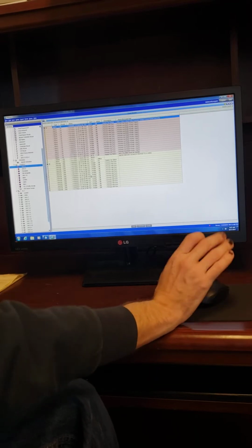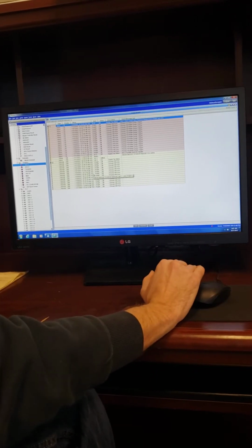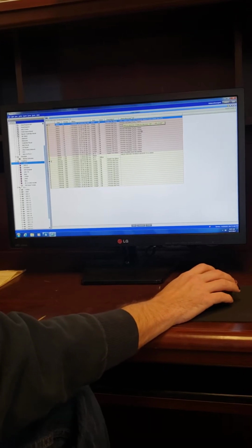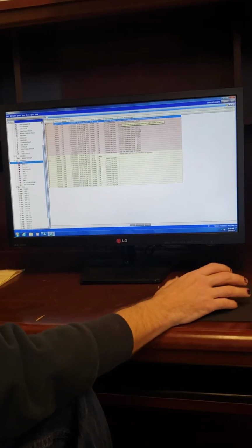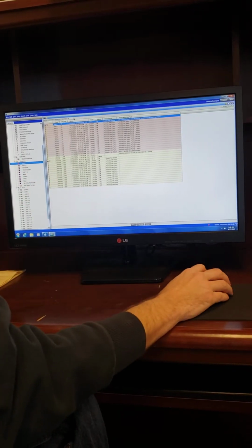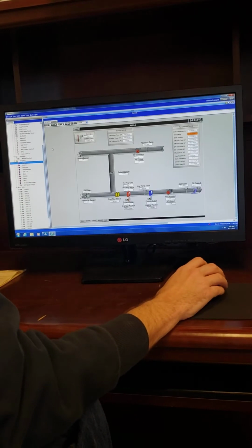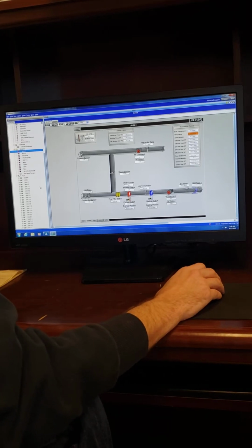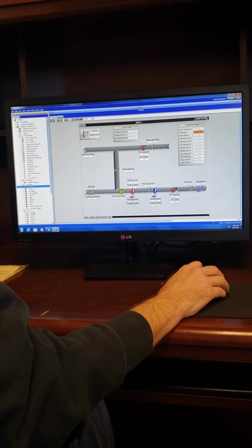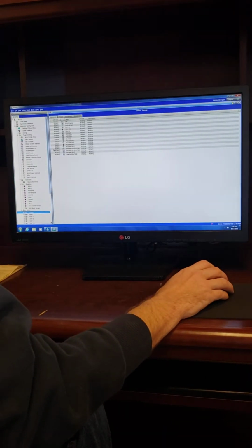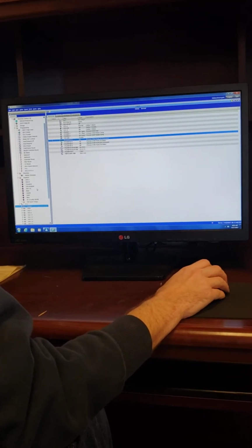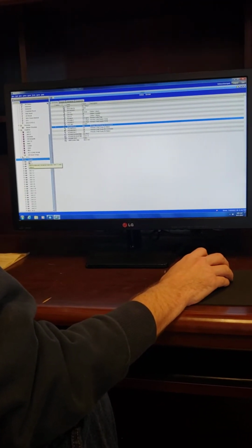So if you ever come in and your commands are on and your supply fan statuses are off, you'll want to go out to the units and check those switches, which I'll show you where they're at. They're both right by the supply fan. So far, that's about everything that I found in your system that's a little wonky. The chilled water system looks like it's been running good. The temperature in here is good.